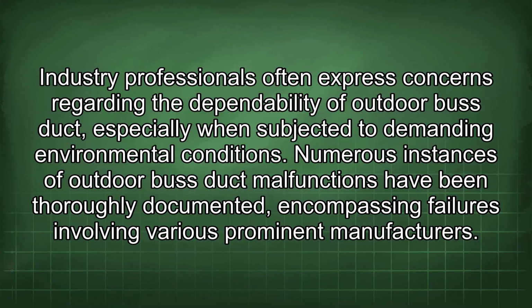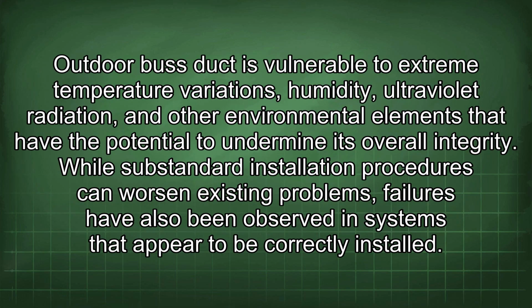Industry professionals often express concerns regarding the dependability of outdoor bus duct, especially when subjected to demanding environmental conditions. Numerous instances of outdoor bus duct malfunctions have been thoroughly documented, encompassing failures involving various prominent manufacturers. Outdoor bus duct is vulnerable to extreme temperature variations, humidity, ultraviolet radiation, and other environmental elements that have the potential to undermine its overall integrity.